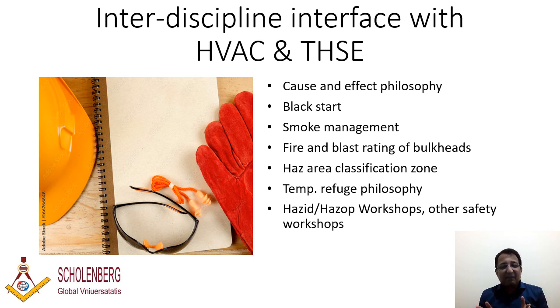If HVAC is there, we need to think about whether it will be recirculation or pressurization, because outside gas should not come inside. So the technical safety discipline and we need to sit together and discuss: if a fire happens, should the HVAC system work or not, should the fresh air damper close, should pressurization be considered, and if gas leak happens outside the platform, should the system work or should it shut down.